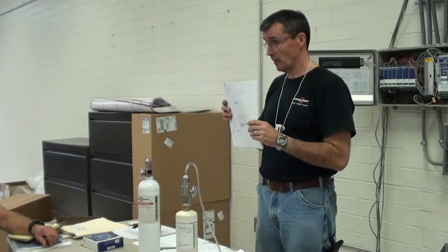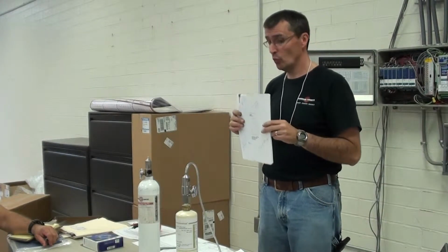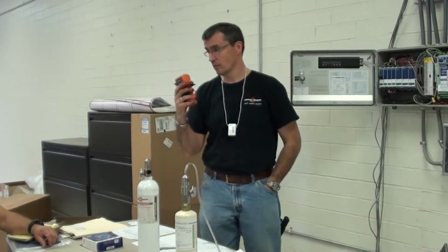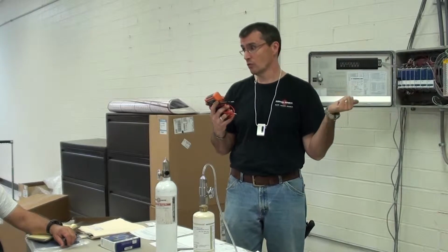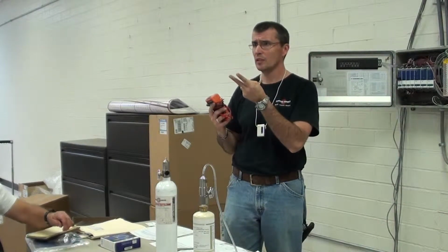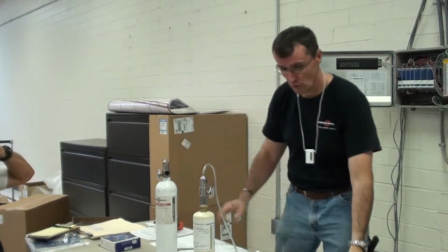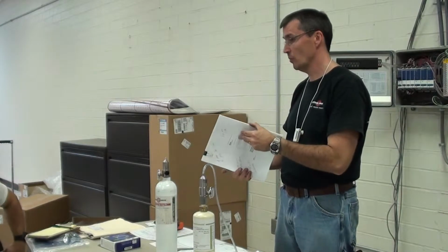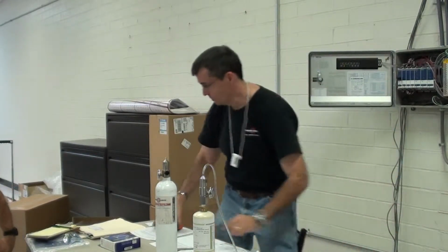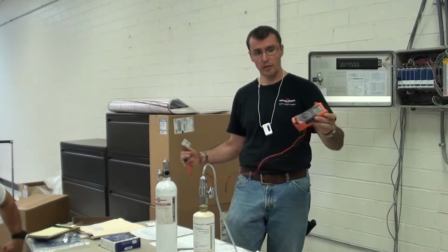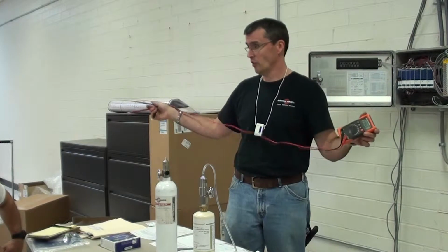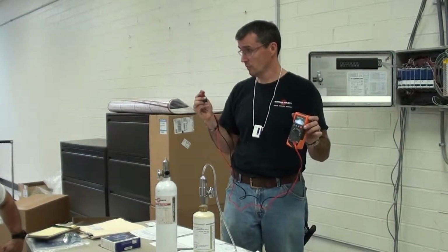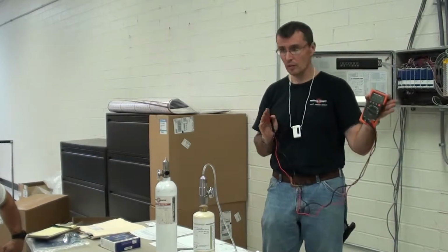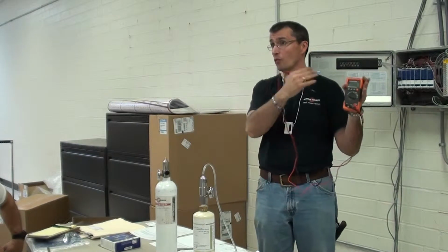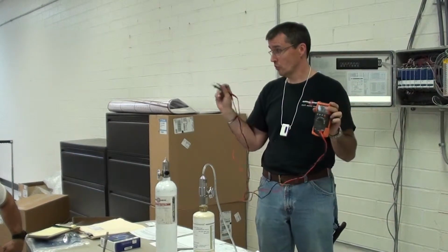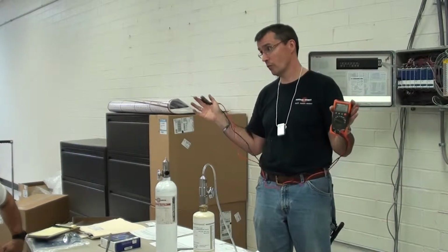Alright, y'all have some of these Xgard manuals left with you. There are 2 test points that you are going to use a voltmeter to read an output signal linear to what's being sent back to your controller system, which is the Vortex. I believe it's TP1 and TP2. That's correct. So it's called test point 1 and test point 2. And it's in your manual and actually shows you a diagram of those 2 test points. Okay? So what you do is you take your voltmeter, you put it on DC millivolt range, and you touch your probes to test point 1 and test point 2. Okay? It's going to range somewhere between 40 millivolts and 200 millivolts. Because remember, you have a 4 to 20 milliamp signal here. So the millivolt output that you're reading on your voltmeter is 40 millivolts to 200 millivolts.